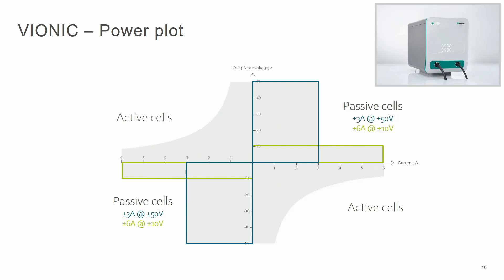As the potentiostat for the measurement, we will use Vionic. I chose this potentiostat because it can apply high compliance voltages even at high currents. This specification is shown in the power plot. In a power plot, the compliance voltage of the instrument is plotted versus current. A potentiostat can either deliver power or it can dissipate the power delivered by the cell.